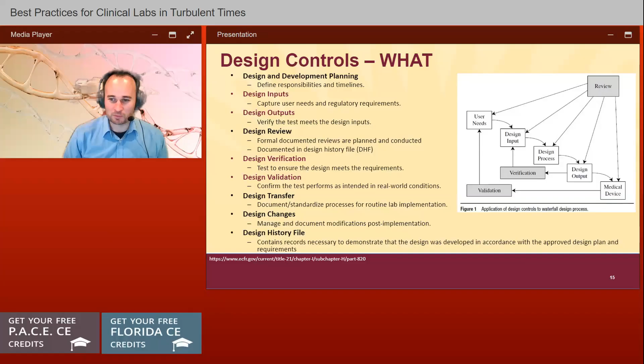You're probably using design inputs right now. You just call them differently. You call it a design requirement or a product requirement, maybe a design input requirement. ISO and FDA call them design inputs. It's all the same thing, but there are 3 kinds of categories of design inputs. Functional inputs. So what does the device do? I test saliva for COVID. What are its inputs and outputs, like the sample input? What are the results outputting?